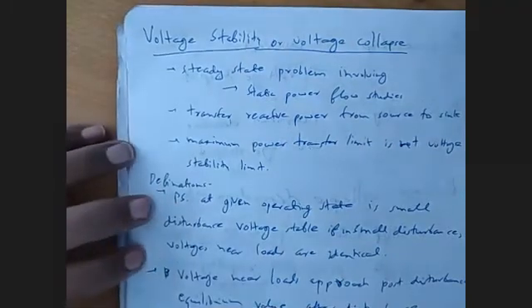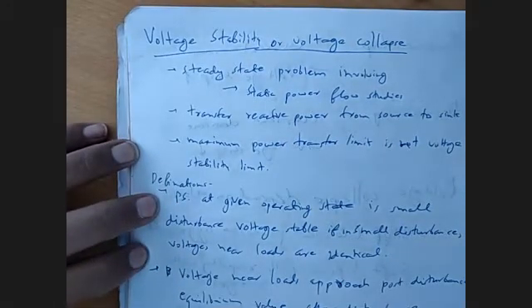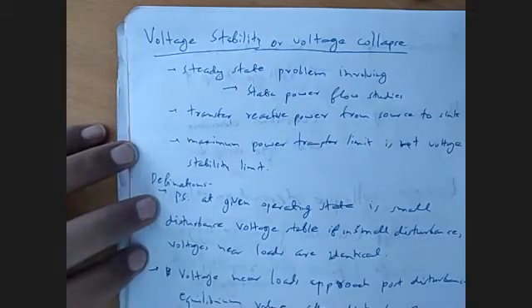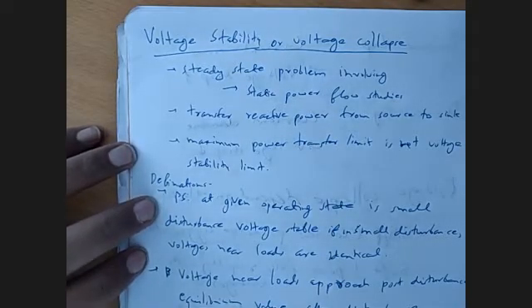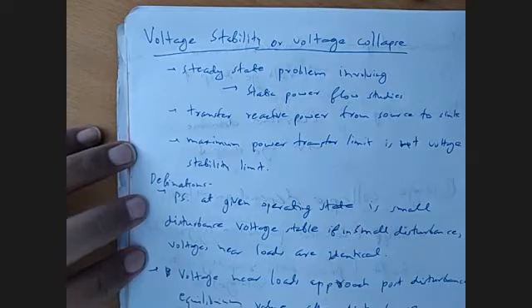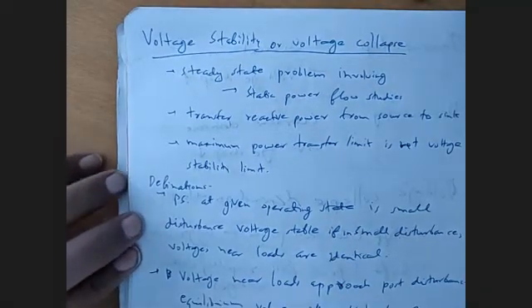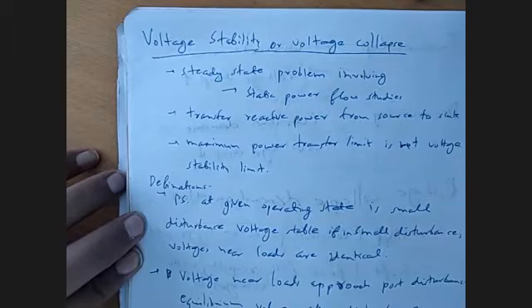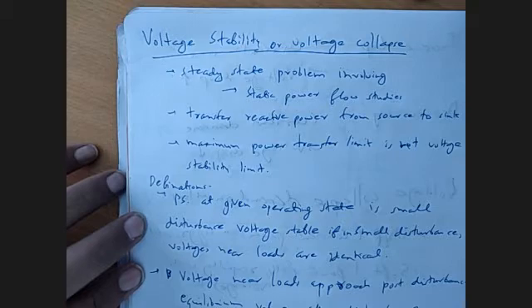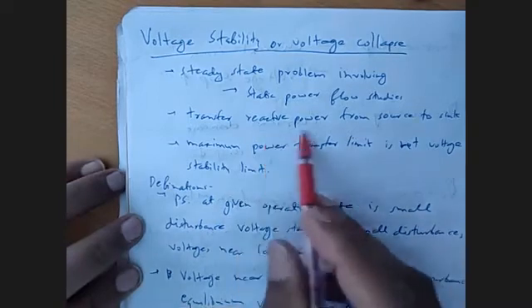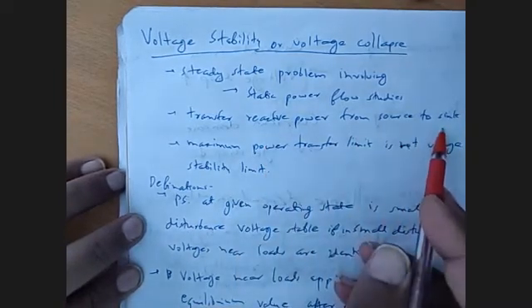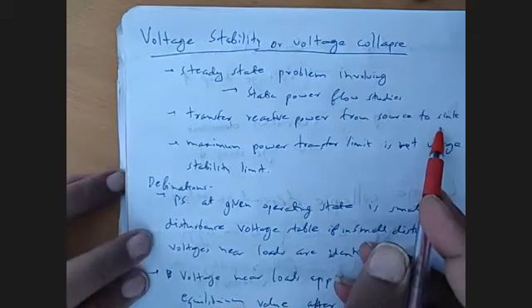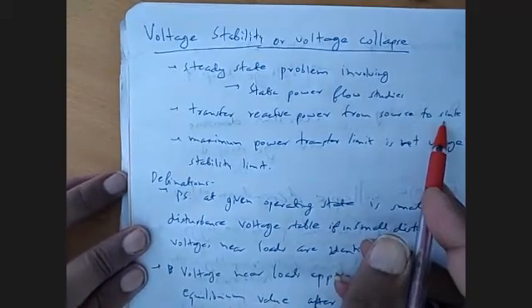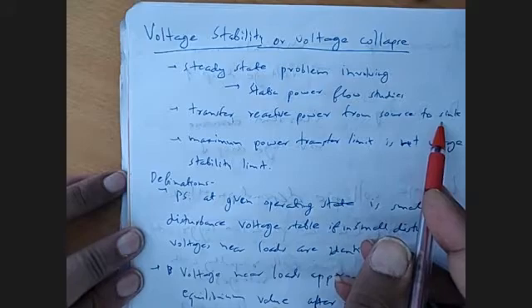So voltage stability is a steady state problem which involves steady state power flow studies. And generally when we are talking about voltage, we are discussing again and again that voltage means reactive power of the system. So voltage stability will indicate the transfer of reactive power from the source to sink. What is the ability of the system to transfer the reactive power from source to sink?